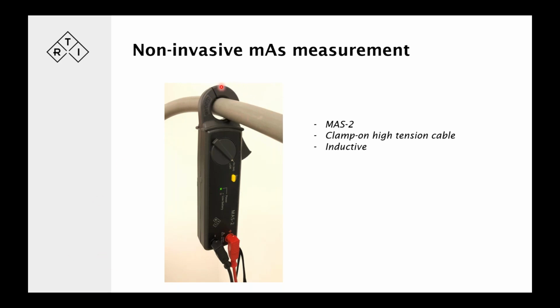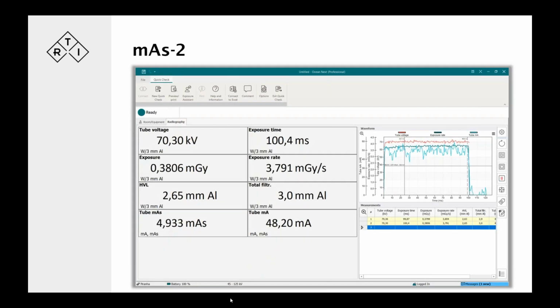The way it works is it clamps on to a high tension cable. You zero it to get rid of any capacitive charges in this configuration here. The cables here are attached to a Piranha, which could be in the beam. And you capture through the inductive properties around the high tension cable, you're able to pick out the mAs readings. And this is what it looks like. So you've got the Piranha in the beam, and so you have the normal Piranha values in these displays, and then attached, the MAS2 probe gives you the mA and the mAs based on the exposure time values that we've received.